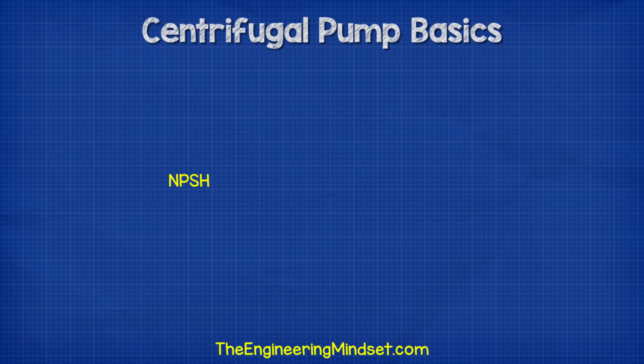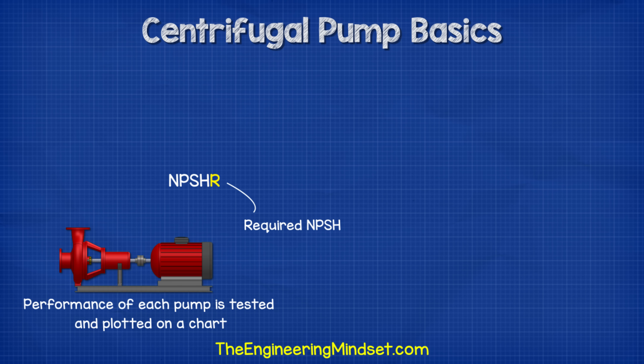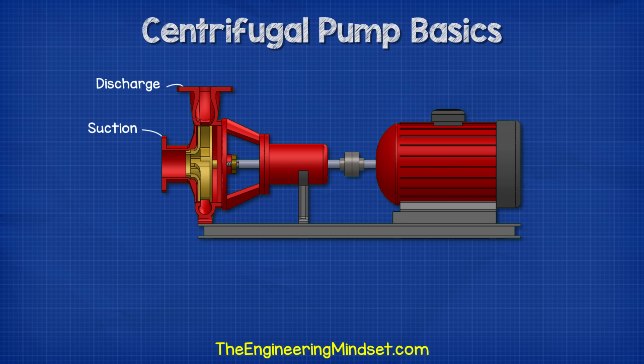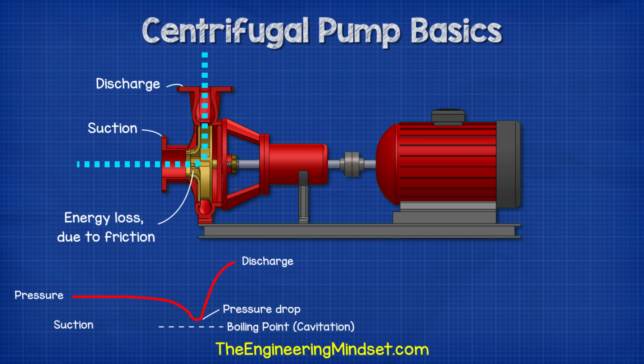A term you're going to hear is NPSH, which is the acronym for Net Positive Suction Head. There are two values: the NPSH-R and the NPSH-A. The R is the required NPSH — each pump is tested for this value and it can be obtained from the pump manufacturer via the pump's operating chart. The A is the NPSH available, which depends on the installation of the pump and needs to be calculated, considering things such as installation type, elevation, liquid temperature, and liquid boiling point. The available pressure should always be higher than the required value.